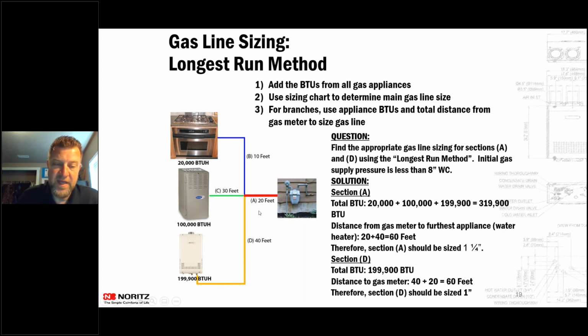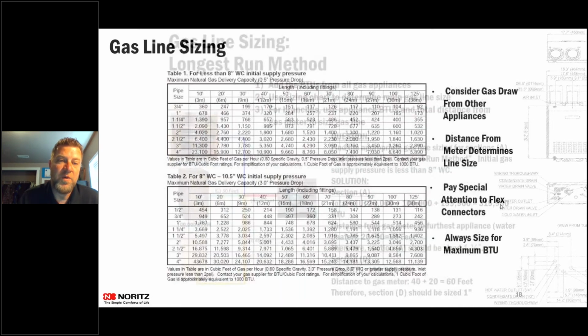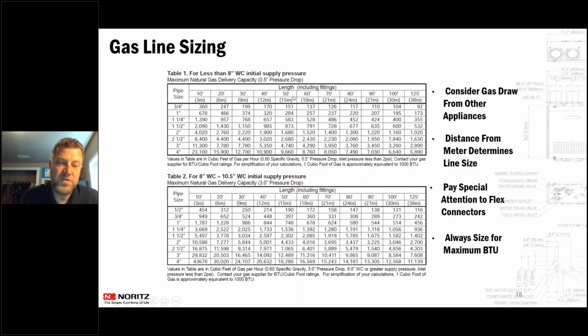So within this diagram here, the total BTUs is 20,000 for that range, which usually ranges are about 60,000, 100,000 for that furnace, and 199,900 for that tankless water heater. So distance from here to there, if you go back to this chart, if we're at 319,900 BTUs, and we go back to this half-inch pressure drop chart, which is here in Utah, we're 60 feet, we're 319,000 BTUs. Our main line would have to be 1.25 inches coming in.